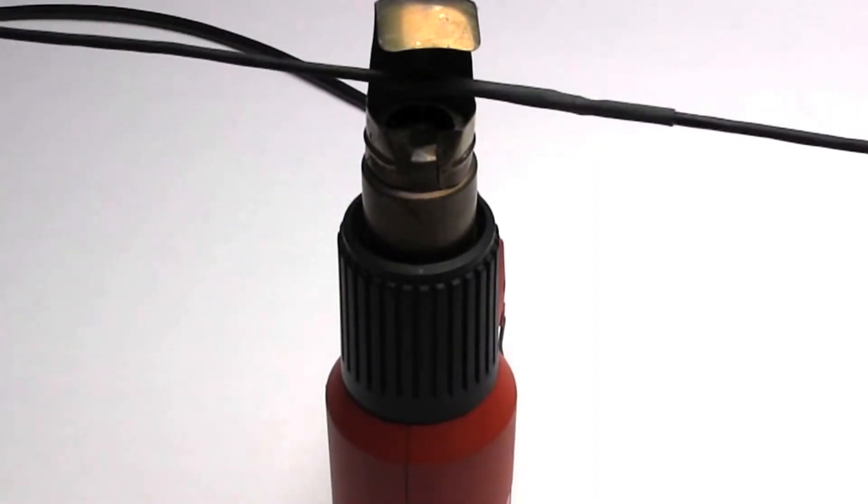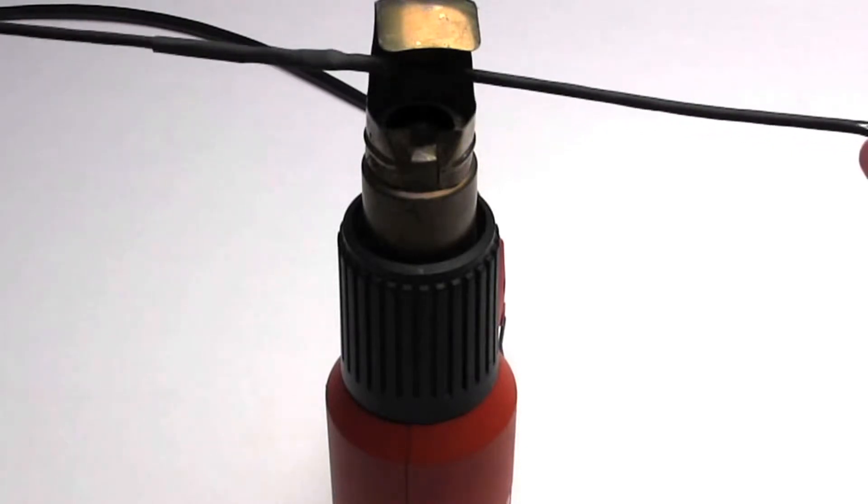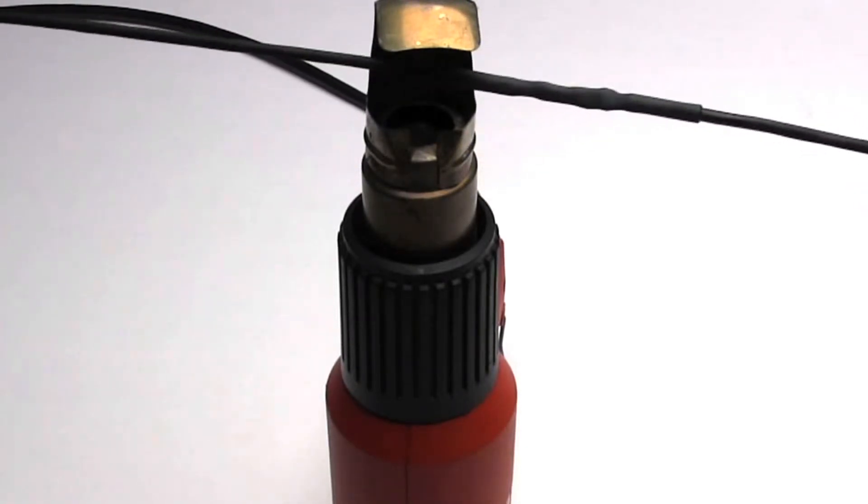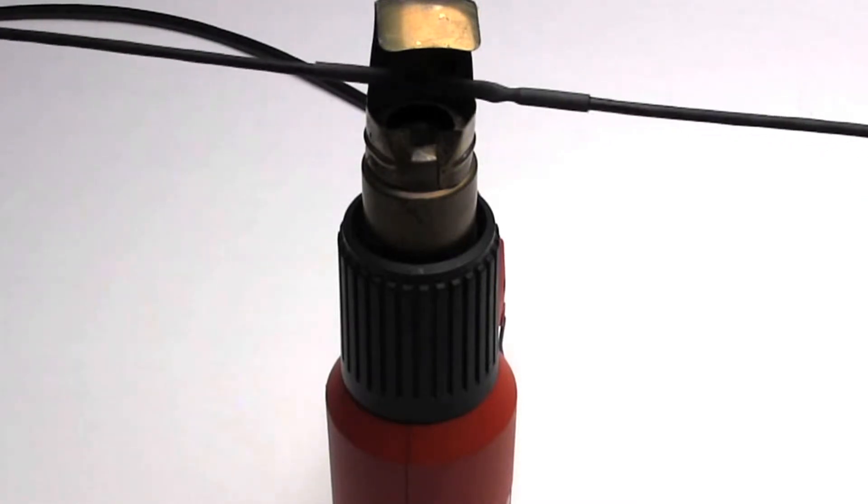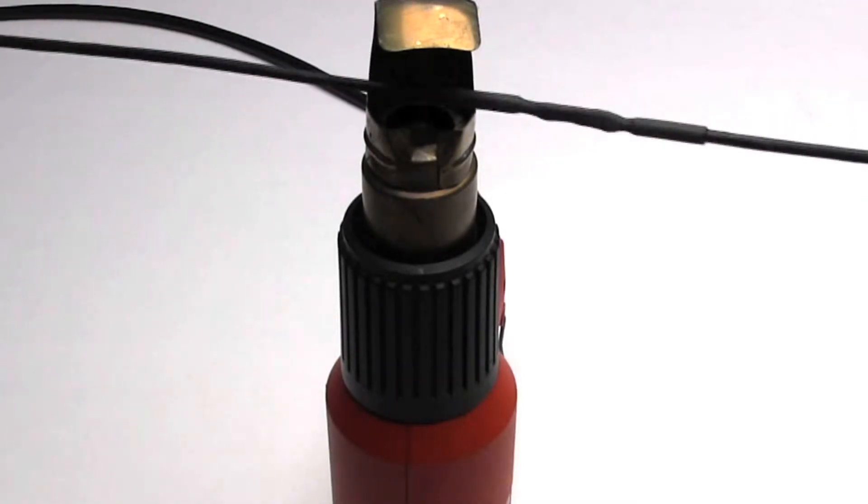Use the heat gun and notice the heat shrink forming tightly to the cable and splice. The adhesive lined heat shrink will have a glossy look once the glue has flowed. Be careful not to overheat the heat shrink. If overheated, it will start to warp and eventually melt away.